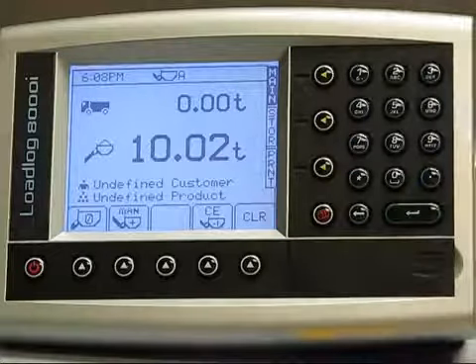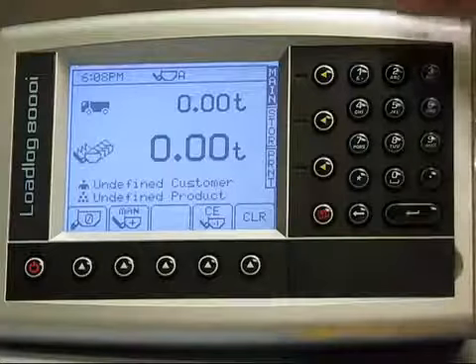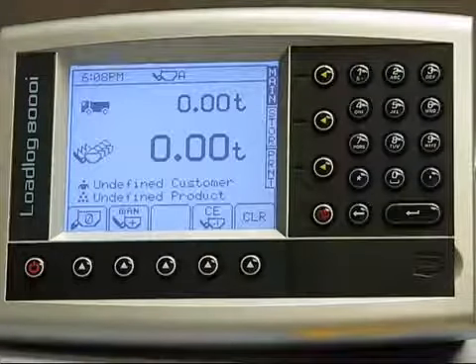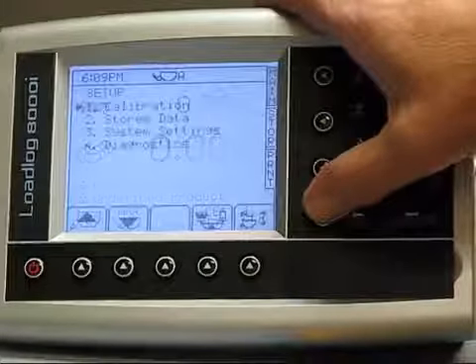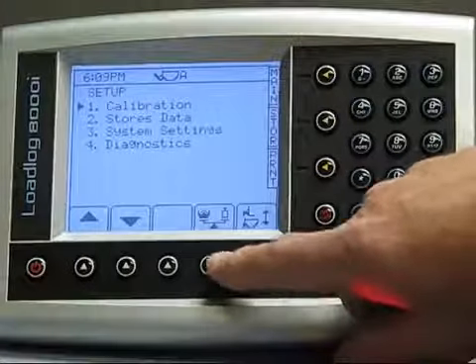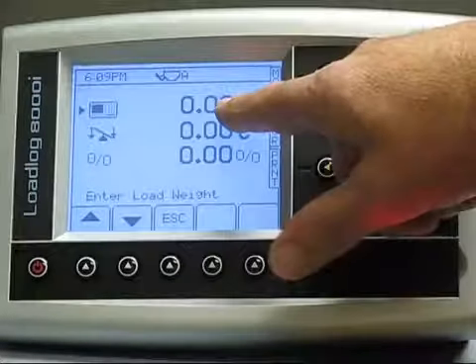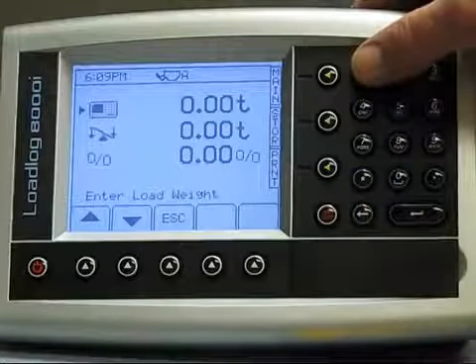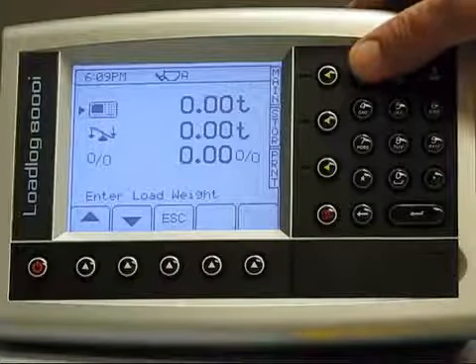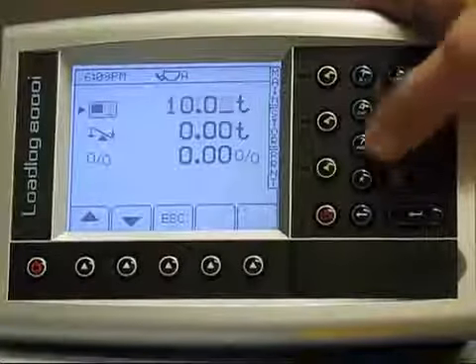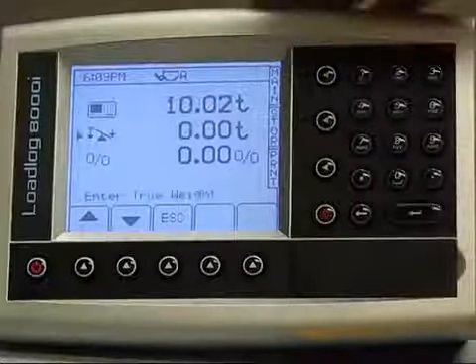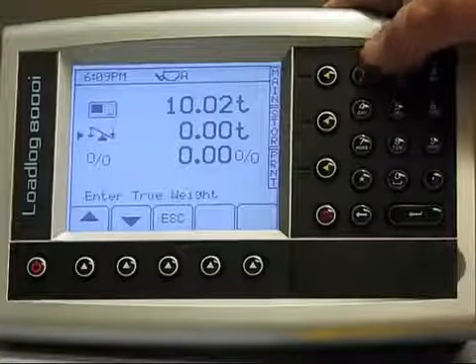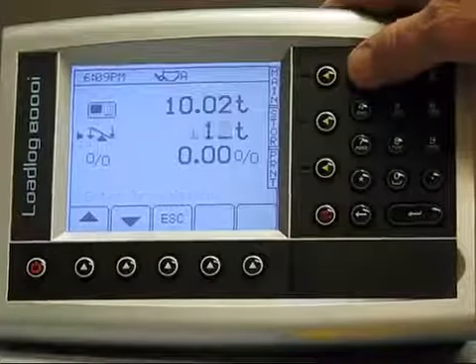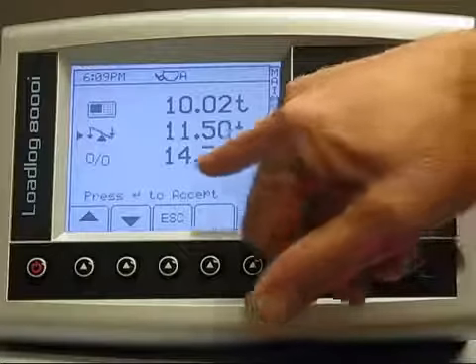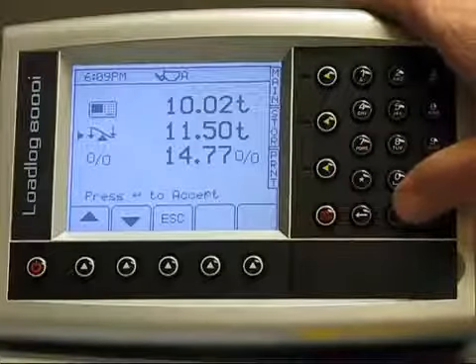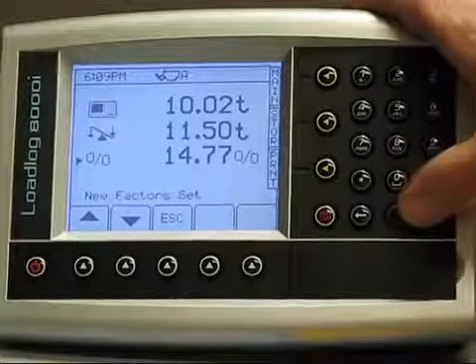At this point, if we need to nudge the scale, which would be the final adjustment in the calibration, simply put, once we know what that weight actually is, we would press the menu key, which is the red key. We would press the second button from the right hand side at the bottom, which has a scale on it, and we would very simply tell the Loadlog 8000i exactly what difference there was. In this case, we know that the scale read 10.02 on the 8000i, and we ran this load across an actual truck scale, and we discovered that it was 11.5. This is our example. That is a 14.77% adjustment, and we have to press the enter key to accept, and new factors are set.